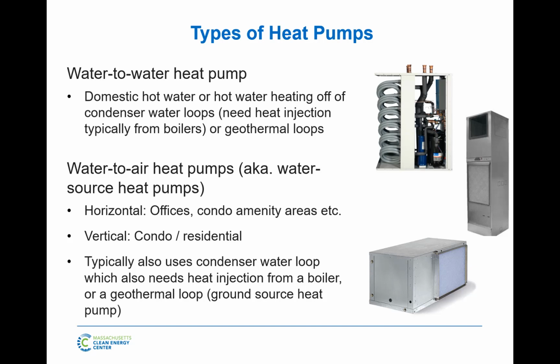Now, usually a water source heat pump is, again, a refrigeration cycle, everything's in here. The compressor, the expansion valve, the evaporator, and the condenser, they're all in here. There are 2 heat exchangers. One is the coil with the air. One is a coaxial heat exchanger with the water. So these things interact with what we call a condenser water loop.